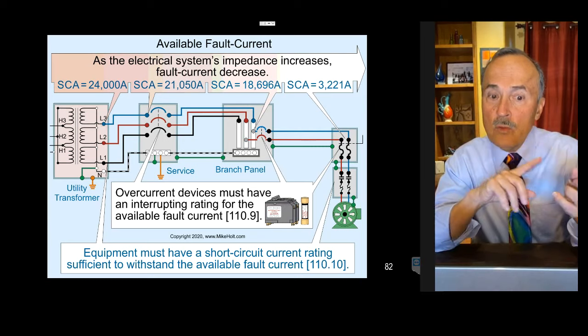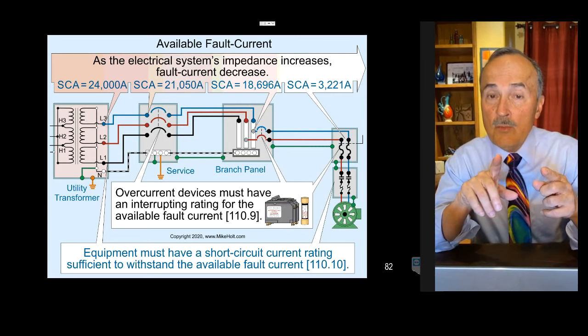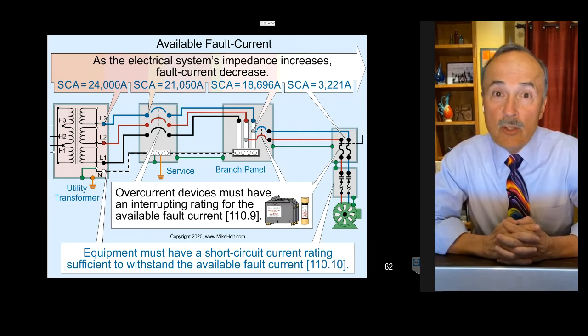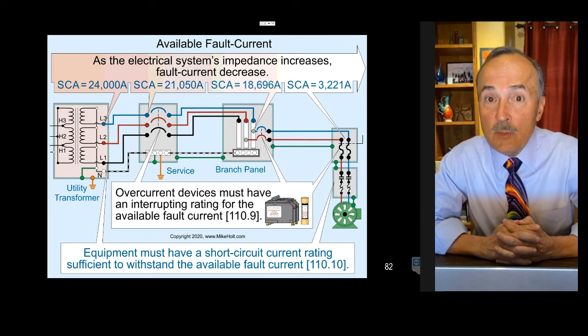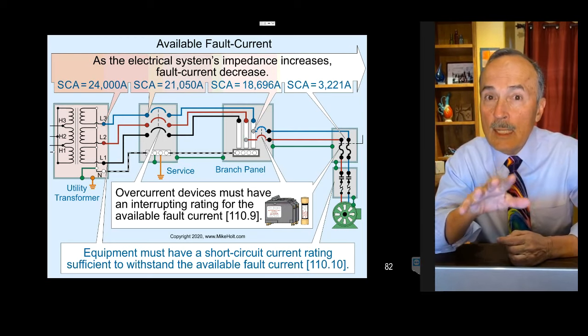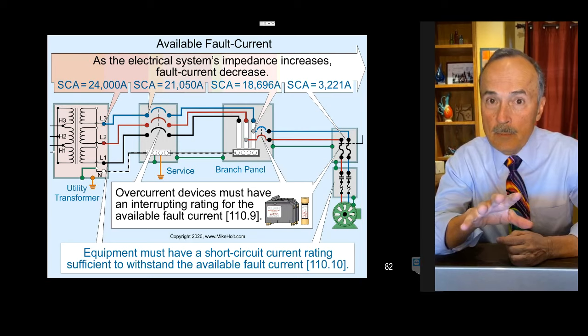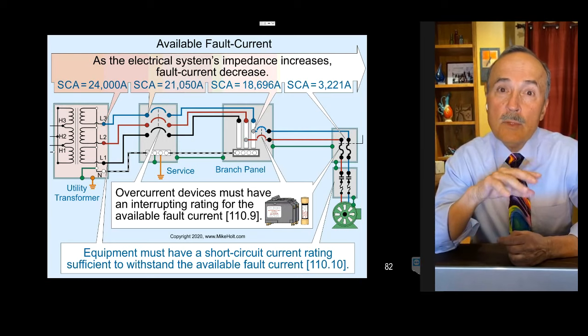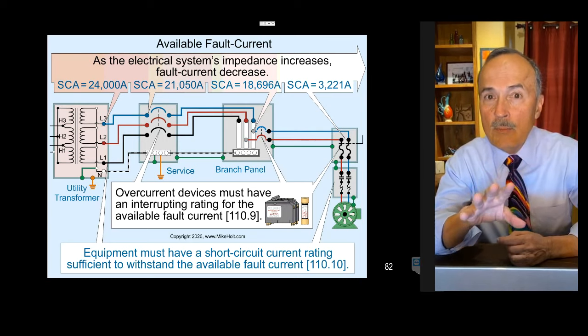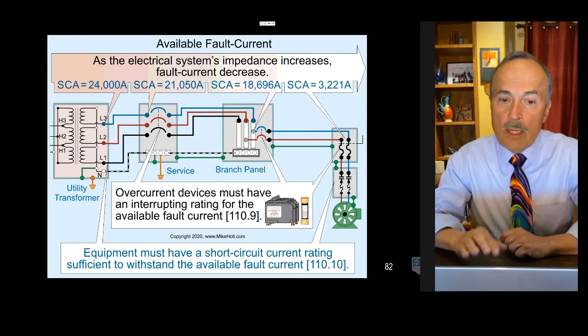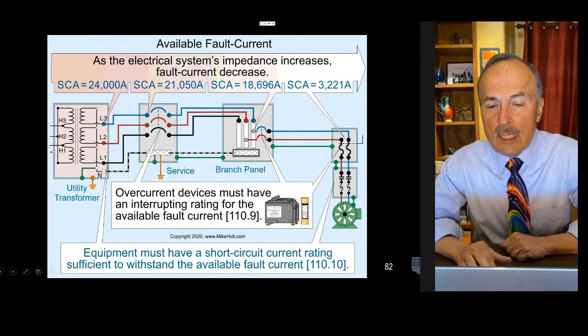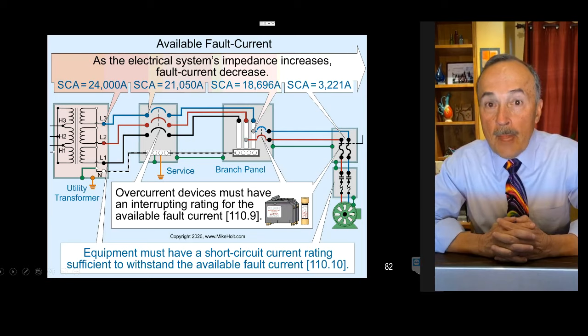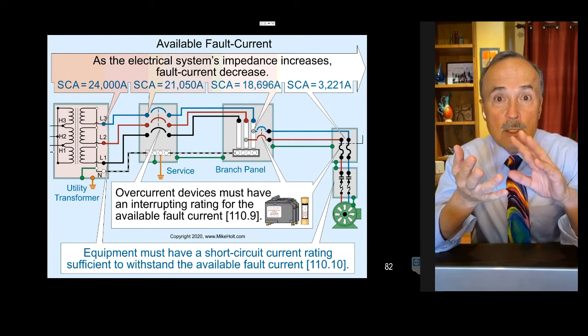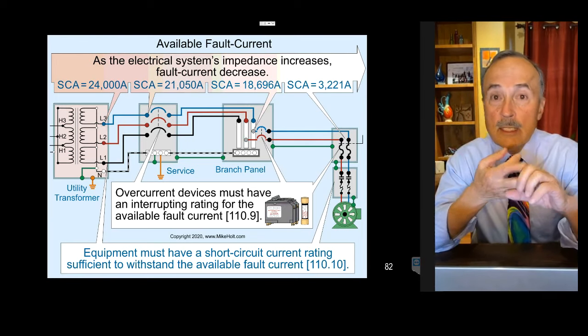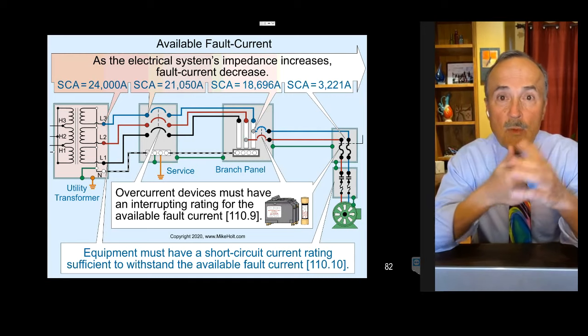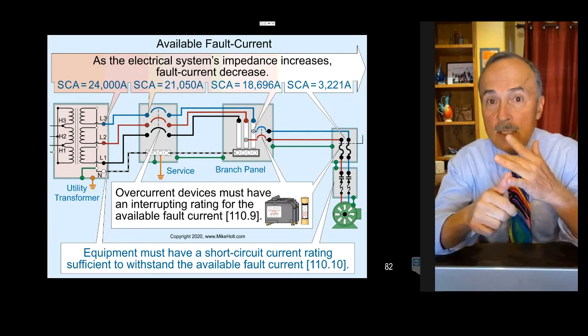Great. But you know what? The most common, well, I say most common, depending upon where you are in the world, but generally most gear is rated 10,000 amps available fault. Well, if you have 21,000 available fault on the line side, then you better make sure you have equipment that is suitable for the available fault. That rule is 110.10. Okay? And then we also have to be worried about 110.9, that's interrupting ratings, but I'm not going to get there. Now watch this.